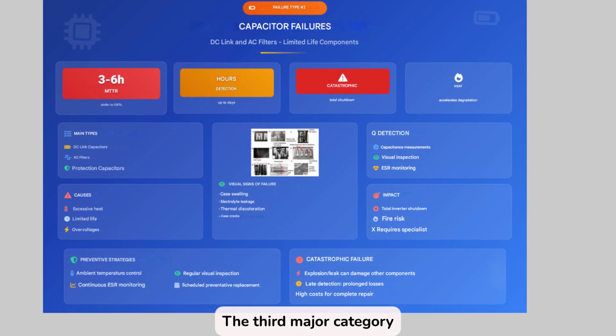The third major category of inverter failures is capacitor failure. Although not the most common, their impact is very high and their danger should not be underestimated. A failure in these components can completely shut down the inverter, affect other critical system elements, and, in extreme cases, pose a fire risk. It is important to understand that capacitors, especially DC link capacitors and AC filters, are components with a limited lifespan that degrade cumulatively and silently. Therefore, by the time the failure is detected, it is often too late, and the technical and economic consequences are already underway.